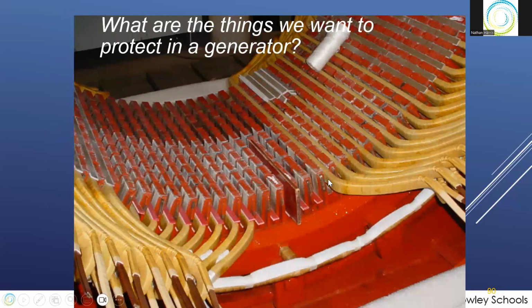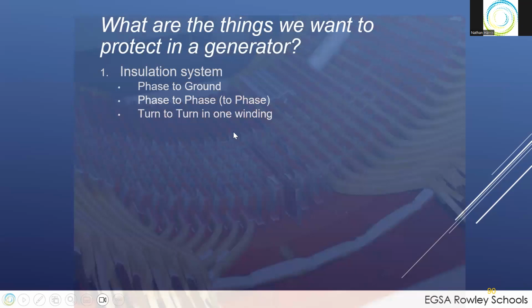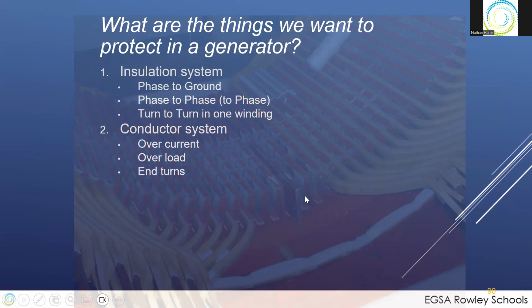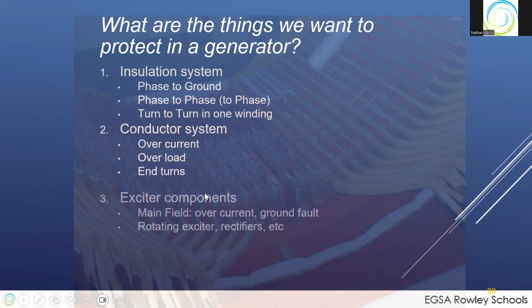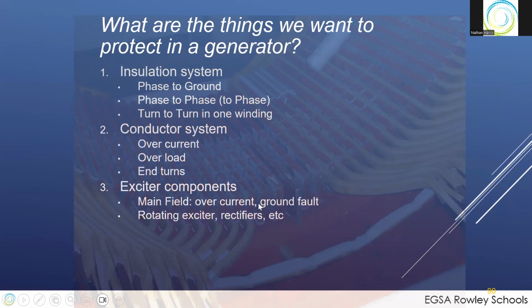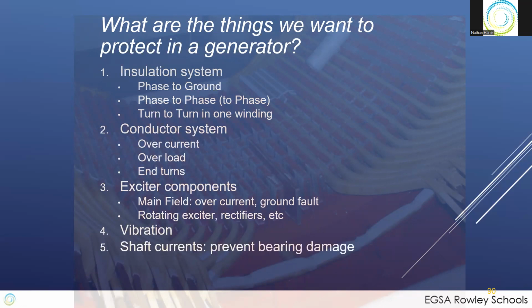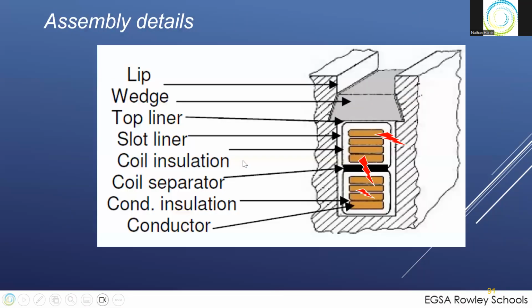We're trying to protect in the generator the systems we talked about the other day: the insulation system, phase to phase, phase to ground, turn to turn, the conductor system against overcurrent, overloads, and the end turns across here, and the exciter components that are out there too. So we're trying to protect these systems in our generator. Of course, vibration as well, but that's a third-party aftermarket. We don't do that directly. And of course, shaft current. You want to protect against that as well, and that prevents pitting on the journal bearings. We'll talk about that more later if you want to.